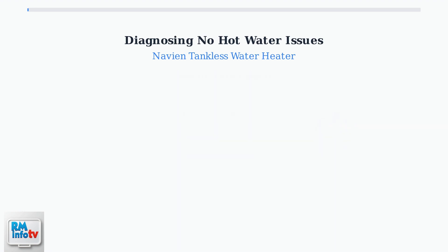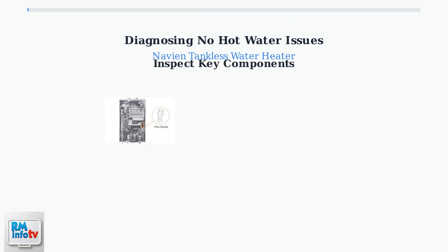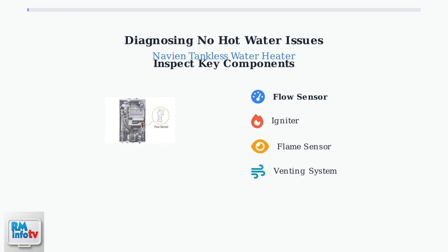If the reset doesn't resolve the issue, inspect key components. The flow sensor detects water movement and signals the unit to ignite — check for damage or blockages that might prevent proper operation. Also, examine the igniter for proper spark generation, the flame sensor for detecting combustion, and the venting system for proper airflow. These components work together to ensure safe and efficient hot water production.